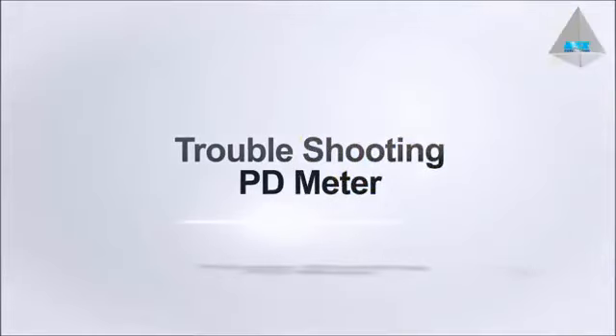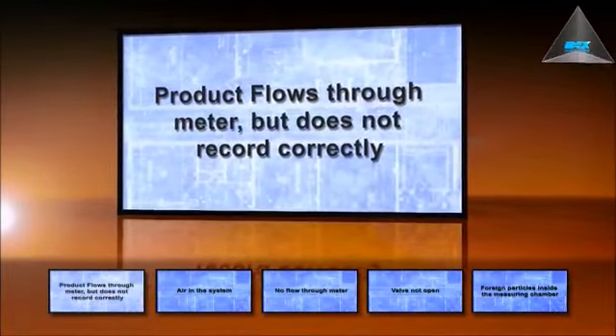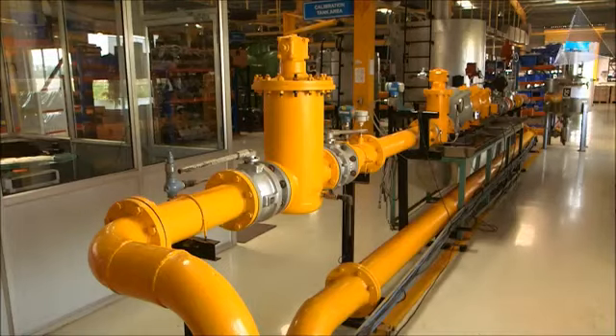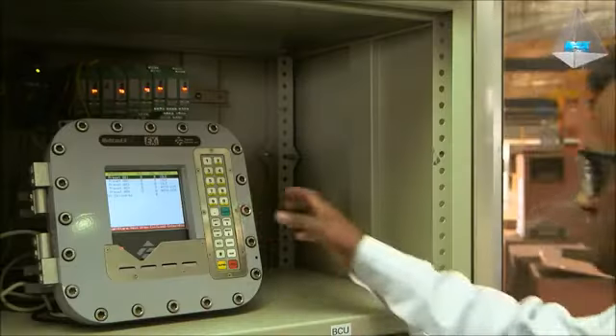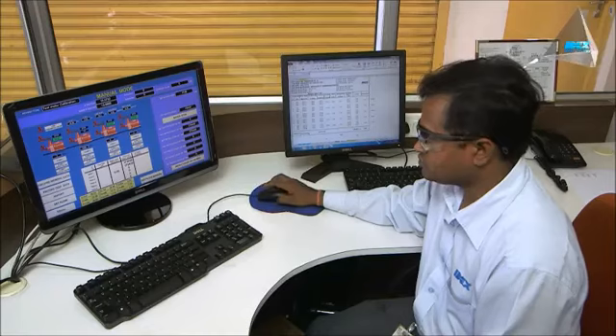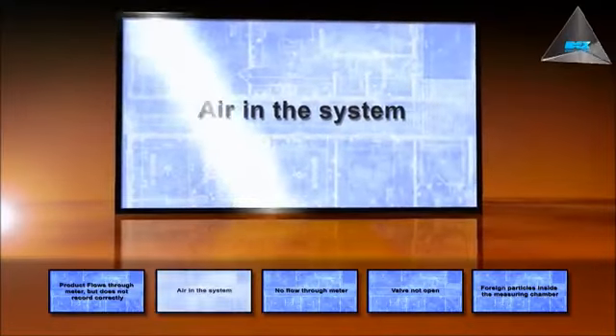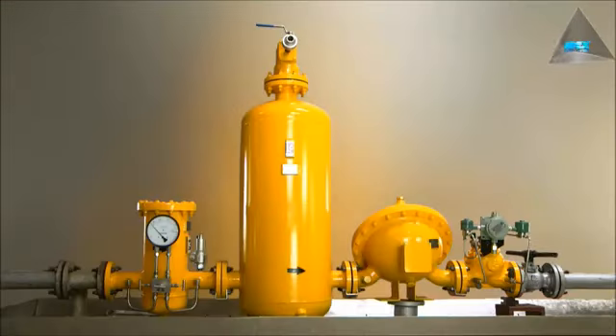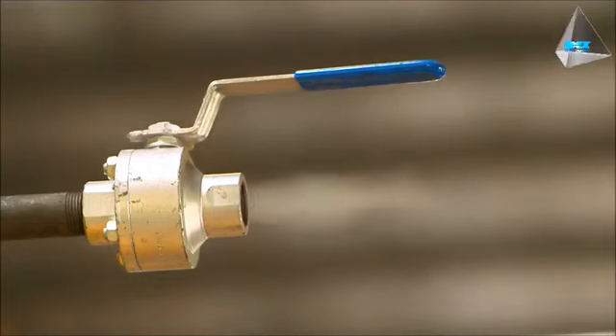Troubleshooting PD meter. Product flows through the meter but does not record correctly. Possible cause: the meter is not properly calibrated. Solution: recalibrate. Air in the system. Solution: ensure air eliminator is installed upstream of meter and venting entrapped air through its ports.